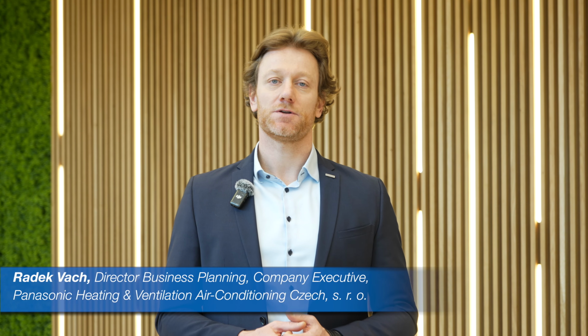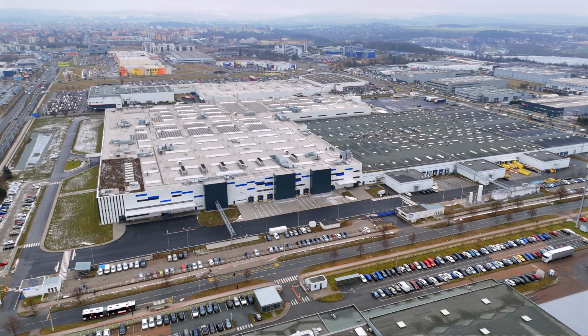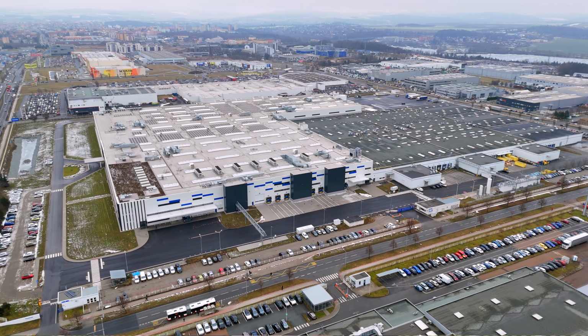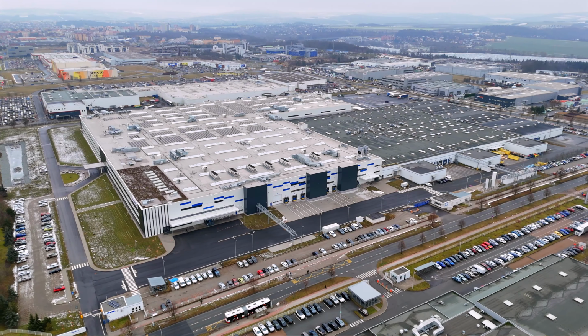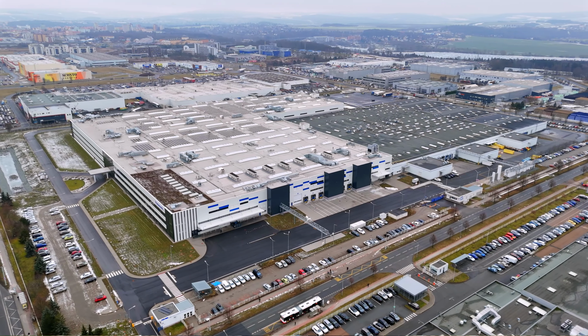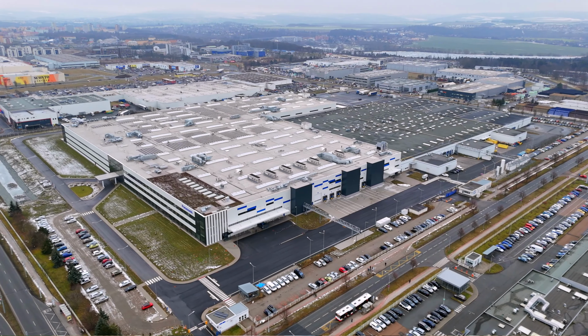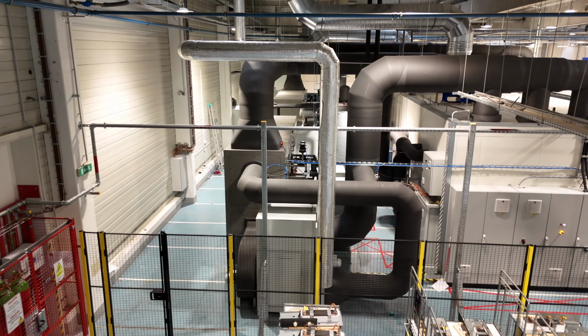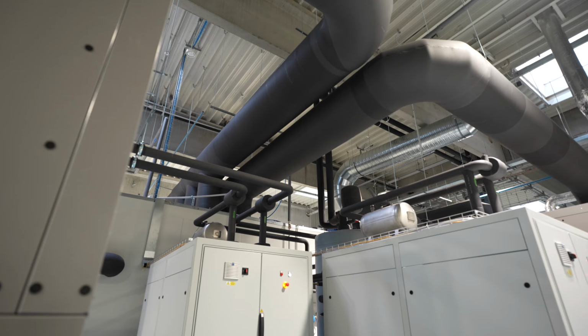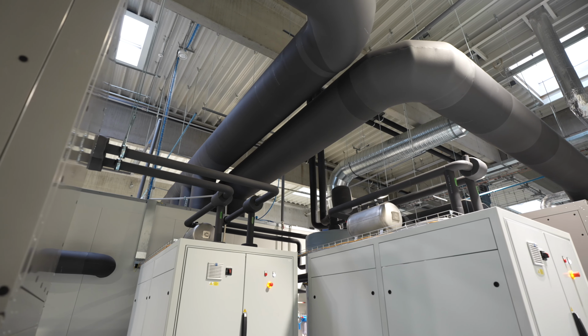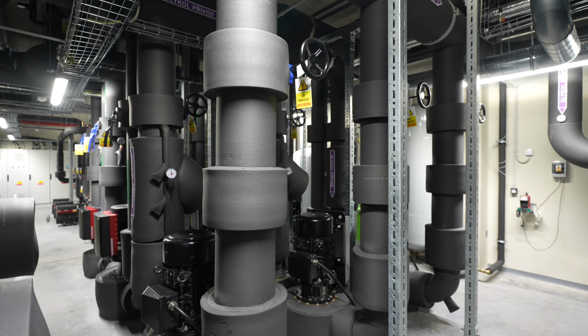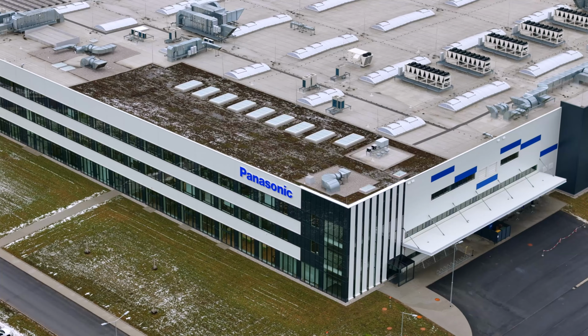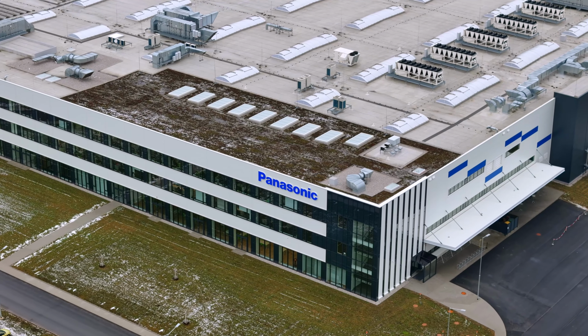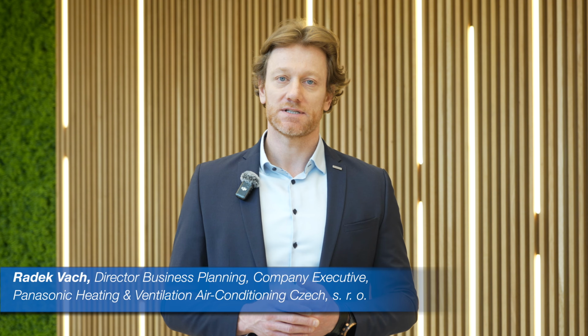Construction of the new Panasonic factory in Pilsen, intended for manufacturing Aquarea heat pumps, brought many challenges. One of the challenges was how to ensure heating and cooling of not only administrative and production areas, but also how to ensure so-called technological cooling, requested mainly for testing of produced units. Overall cooling capacity was relatively high, specifically 4,800 kilowatts.